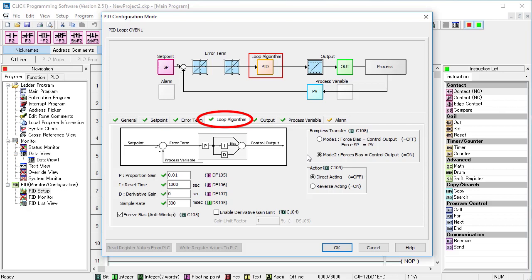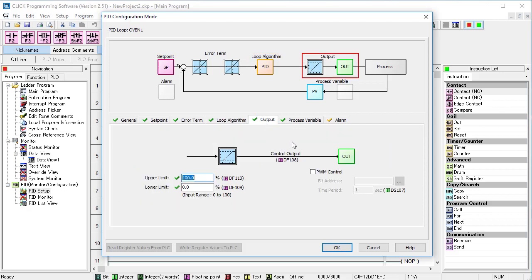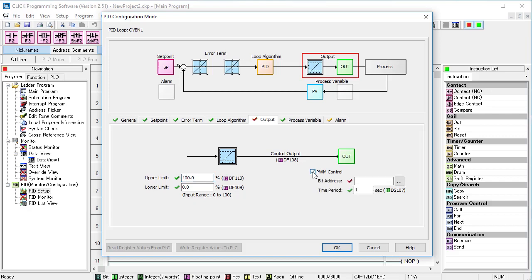We have a green checkmark, so let's move on to the output tab. We can change the output scaling if we need to. We don't need to change it from the default 0-100% because we want to drive a PWM output which needs 0-100%. And we want that PWM signal to control output Y1 which goes to the solid state relay. A 1 second period for the PWM signal is fine for our heating application.